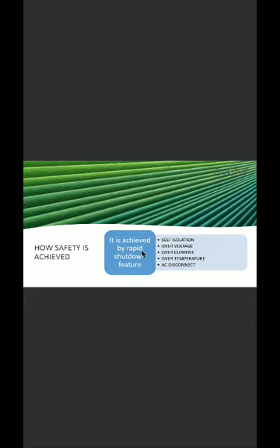So it is actually the rapid shutdown. The rapid shutdown we discussed before is getting the module output, the optimizer output voltage, to zero. How can we get that? Through self-isolation. If there is any over voltage, over current, or over temperature in the string or in the module, then TIGO will drag the output voltage down to zero. One more condition that drags it down to zero is AC disconnect. When there is a disturbance in AC or there is no power supply, TIGO will take the module output voltage to zero.